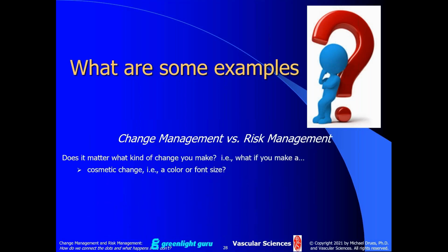So let's take a look at some examples. We can change a medical device in a litany of different ways. For example, we can make a cosmetic change. What if we change the color of the device? Or what if we change the font size of a display? What are the potential implications on risk? Well, those kinds of things usually need to be investigated probably by some sort of usability study.